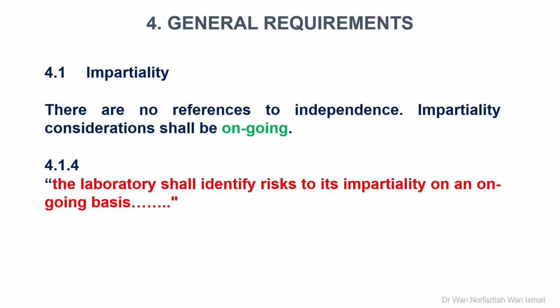It is recommended to write down a document in which, depending on the needs, the following steps should be included: analysis of potential impartiality risk, including risk arising from the laboratory activities, its relationship, and the relationship of its personnel, measures to eliminate or minimize risk concerning impartiality, action plan, design and implement permanent actions, commitment of the laboratory to its integrity through the signature of a statement by the top management. This analysis should be reviewed at the management review and, if necessary, revised.